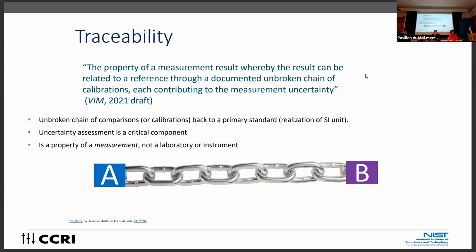One of the colloquialisms that we use a lot is that we have a traceable source. Well, there's no such thing as a traceable source. You have a source where the activity measurement is traceable to a standard. Likewise, you don't have a traceable instrument.